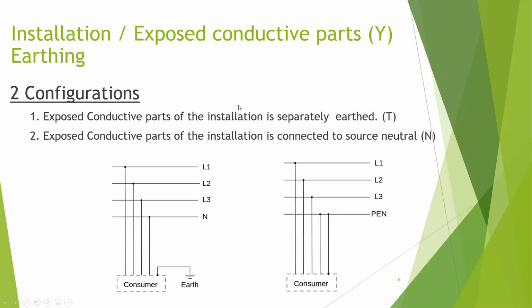Now, installation or exposed conductive parts earthing, this is the one we earlier talked about. And here also we can have two configurations. The first one is that the conductive parts are separately earthed. Separately earthed means this is also T, similar to T in the source earthing. We are directly connecting exposed conductive parts to earth. And the second one is, remember earlier in the isolated one, the neutral was not connected to ground. In exposed conductive part earthing, we are connecting everything to neutral. So that is called N. So we are using the term N for that.